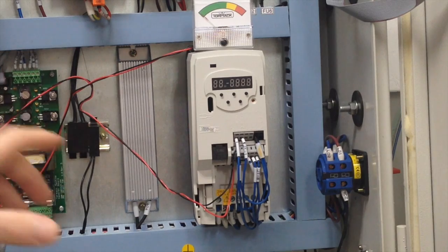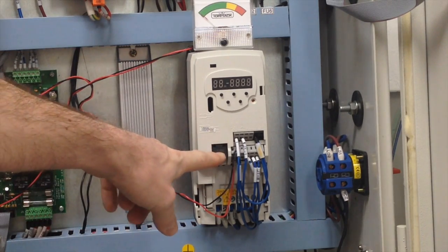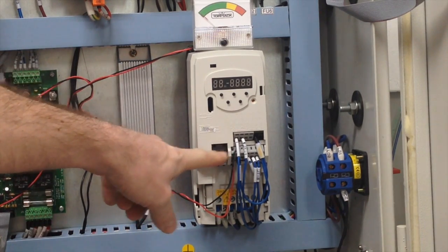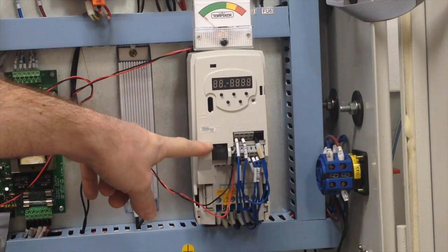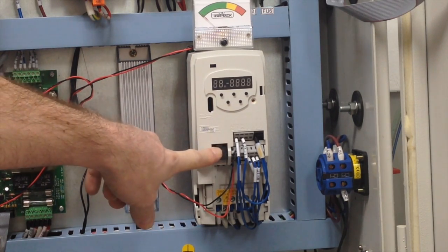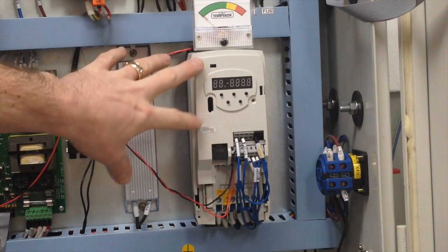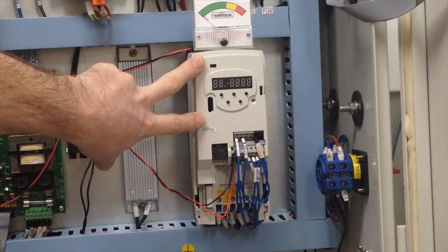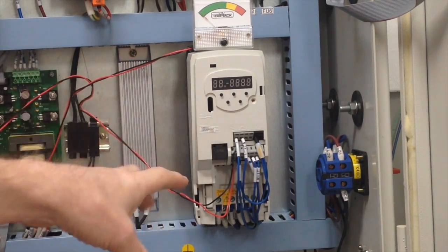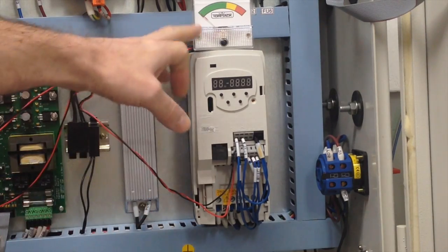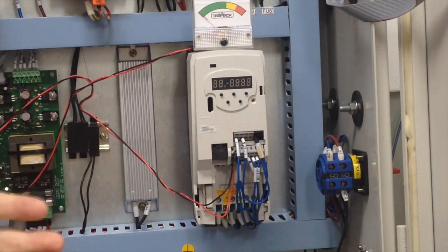What is of far more interest is this little black thing down here. This is an RJ45 port. It's not network. It's RS485, so it's a serial port, and it's running a protocol suite called Modbus RTU. So we can actually send serial requests direct to the VFD and ask directly for parameter sets. And this is where the hack's going to go, okay?